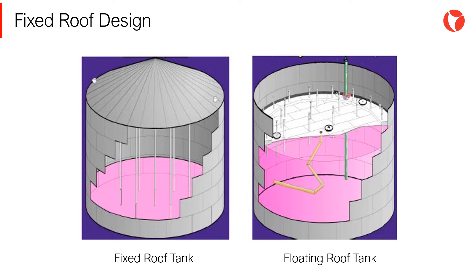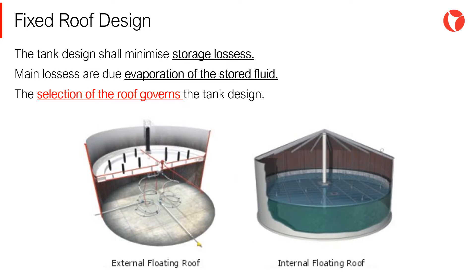When the fluid to be stored is a product that tends to evaporate at the operating temperature of the tank, a vapor chamber is created between the level of the liquid and the tank roof. To eliminate this vapor chamber, floating devices resting on the liquid are used. The tank design shall minimize storage losses, as the main losses are due to evaporation of the stored fluid. The selection of the roof governs the design.